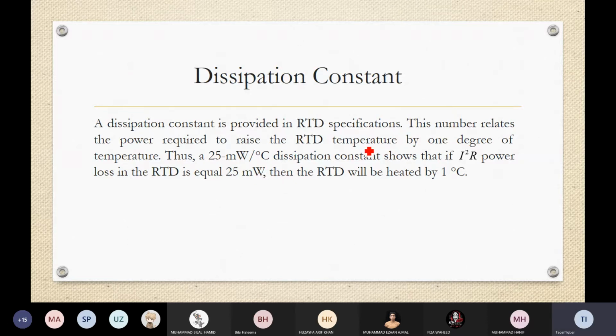And we have to keep that in mind also, that we are going to lose that much power continuously if we are continuously measuring the temperature. So to raise the temperature by 1 degree Celsius in an RTD, we need 25 milliwatts of power. So this dissipation constant shows that if I squared R power loss is equal to 25 milliwatts, then the RTD will be heated by 1 degree. Okay? And this 1 degree would result in error in the actual calculation of the temperature.